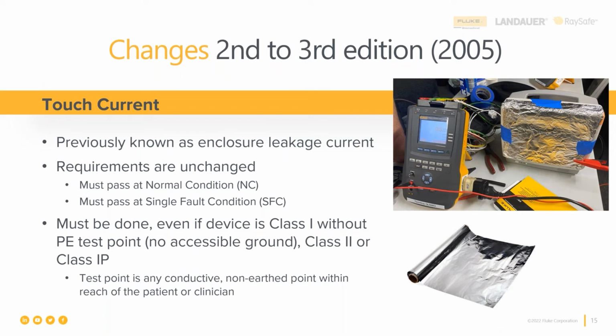And it's touch current because what we're trying to measure here is a what if. What if the patient accidentally touches the medical device that they're connected to? What if the nurse or the doctor touches that medical device while they're touching the patient? Is there a current flow there that could be a problem? And if it is, where is that current flowing and how much is flowing? And so that's why we call it touch current. It's the same test, exactly the same requirements as we had for enclosure leakage or chassis leakage. Same thing. So what must be done? If it's a class 1 without a protective earth test point, a class 2, or even a class IP, which means internal power.